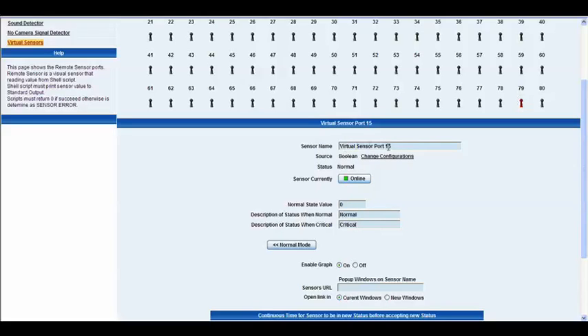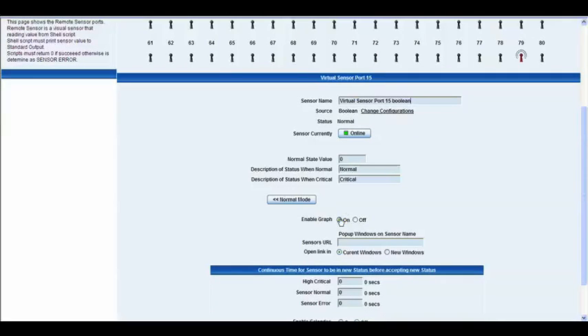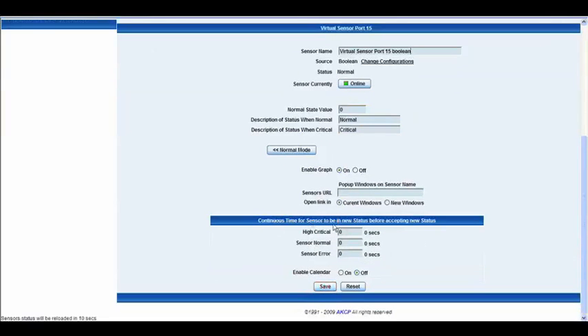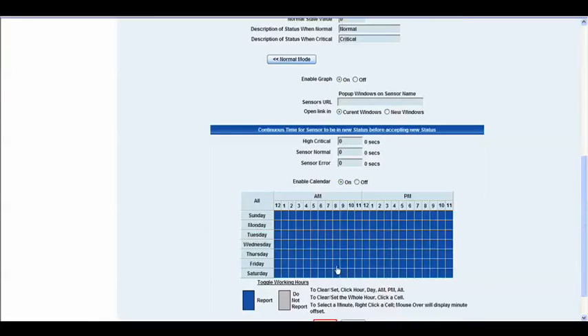We'll leave that as Virtual Sensor port 15 and write Boolean at the end. In our advanced settings, we have our graph options — we can toggle that on or off. We also have the sensor's URL, which you can open in the current window or in a new window. Right below that, you have the continuous time for a sensor to be in a new status before it accepts the new status, which you can change to however many seconds you'd like. For example, if you want it to remain in a High Critical status for 10 seconds before it reports on that status, that's what you would write in that box. Finally at the bottom, we have our calendar options — you can toggle that on or off and select the days of the week and hours of the day in which you'd like this sensor to report. We'll go ahead and click Save.